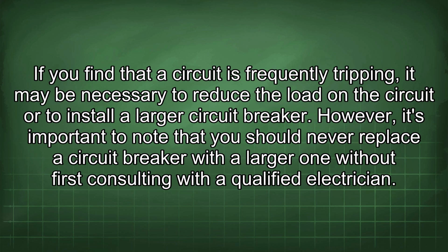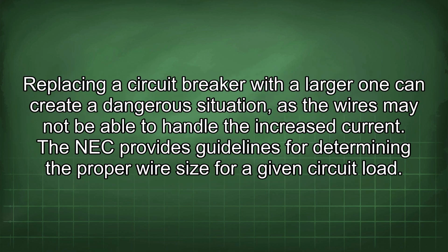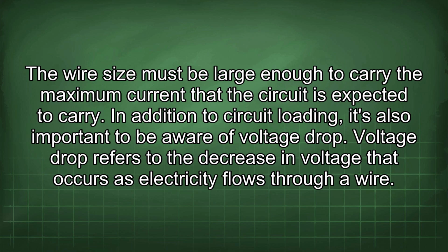If you find that a circuit is frequently tripping, it may be necessary to reduce the load on the circuit or to install a larger circuit breaker. However, it's important to note that you should never replace the circuit breaker with a larger one without first consulting with a qualified electrician. Replacing a circuit breaker with a larger one can create a dangerous situation, as the wires may not be able to handle the increased current. The NEC provides guidelines for determining the proper wire size for a given circuit load. The wire size must be large enough to carry the maximum current that the circuit is expected to carry.